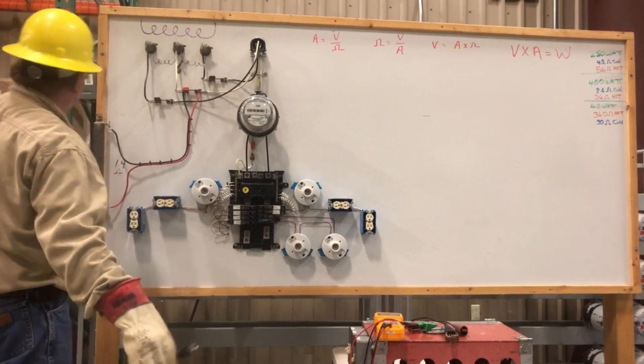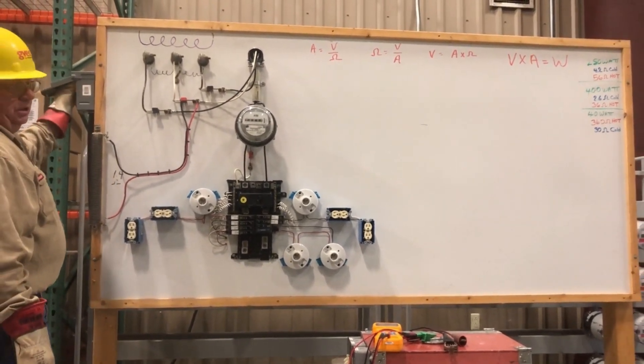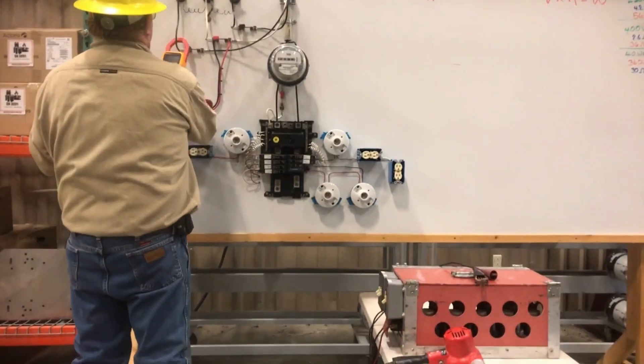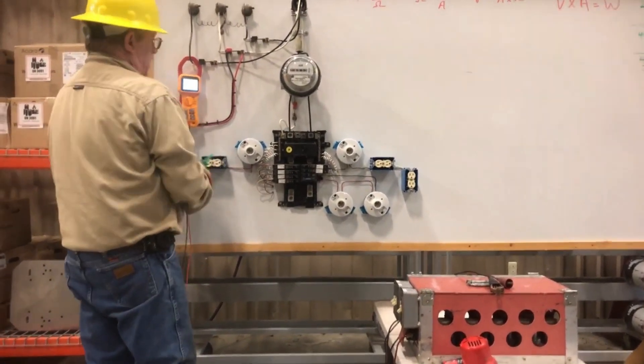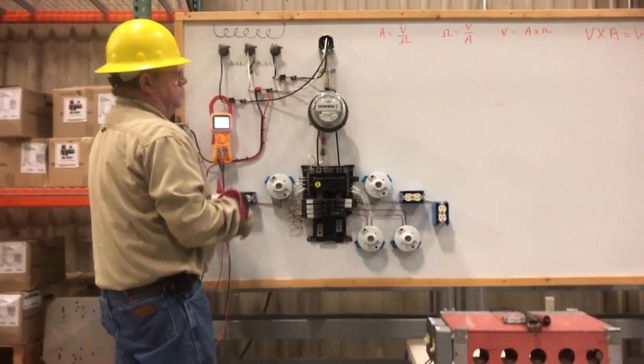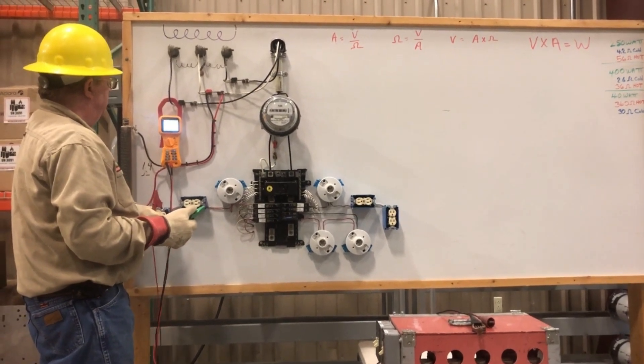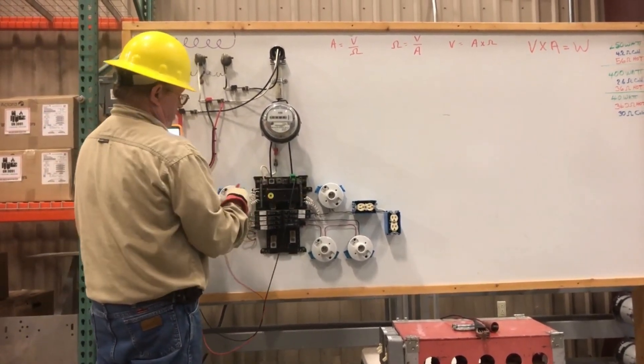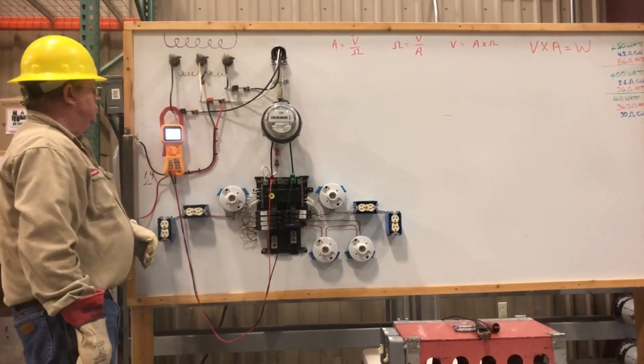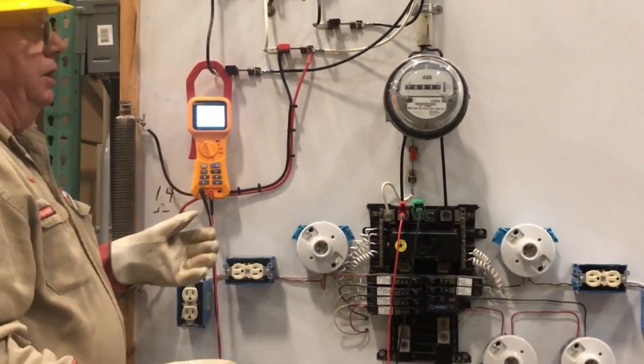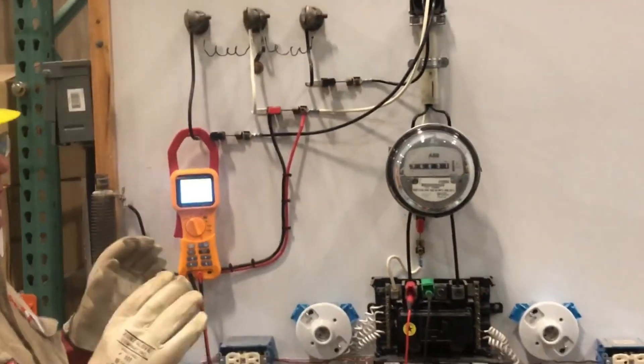So if we went up here today and measured voltage, we have a complaint. The complaint is my lights go dim and they go bright. We shut it off. We measure voltage with the meter in, but there's no load. And we'll measure 241.8, 120.9. And no one could argue. They would say our voltage is good, everybody's happy.